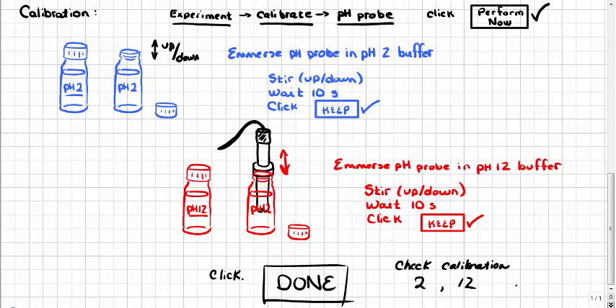Your instructor may also have a pH 7 buffer that you can use to check the calibration of the pH probe. Your pH probe should read something very close to 7 when this solution is checked. However, the pH 7 buffer is not used for calibration purposes.